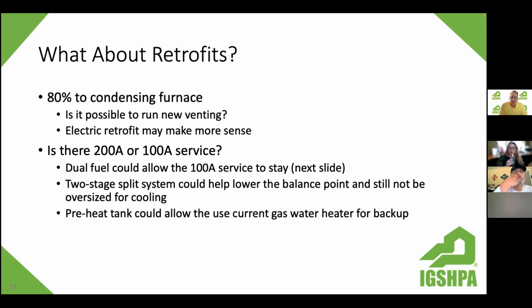We have some options for water heating. A lot of systems have these desuperheaters or hot water assist. With a preheat tank, we could make some hot water, keep that gas water heater offline. And some manufacturers have heat pump water heaters. There are also manufacturers who have water to air units that also make domestic hot water. So there's a lot of options out there as you start to look at the heat pump manufacturers, where we can look at the various product types and make it fit more nicely so we can save some cost on the system, and maybe our incremental costs are not quite as much as what we would expect.